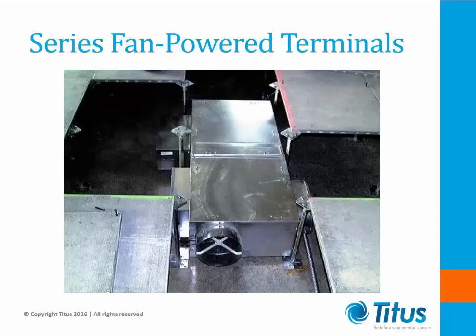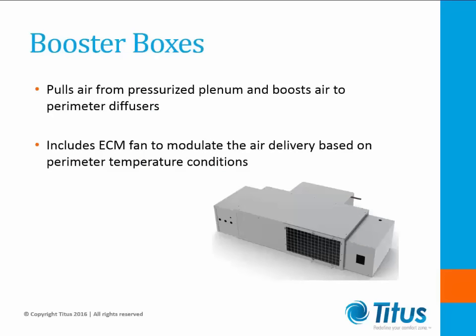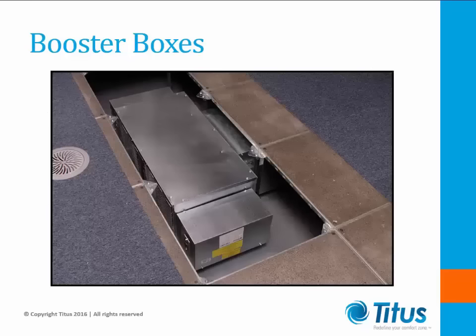Terminal units are typically designed for zero maintenance, but they will eventually need to be repaired at some point in their life cycle. Another type of UFAD terminal unit is known as a booster box — these are fan coils specifically designed to fit into UFAD floor systems. Unlike series fan powered terminals, the booster box typically has no damper to control the supply air mixture or volume; it simply draws air from the floor plenum and then is ducted to supply grills in the floor. The air volume control is handled by modulating the speed of the ECM in response to a wall mounted thermostat or controller. These units typically include either electric or hot water heat.